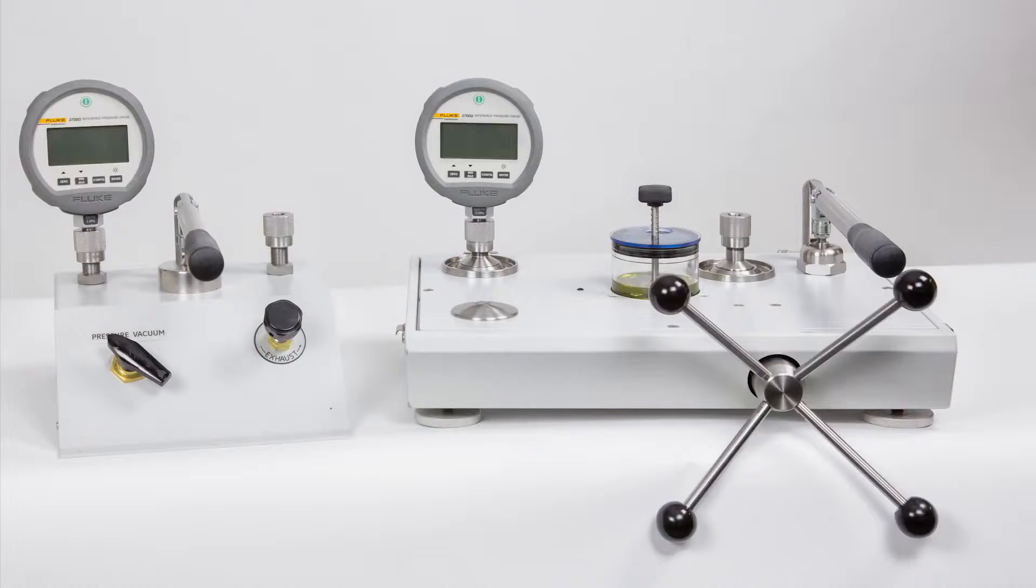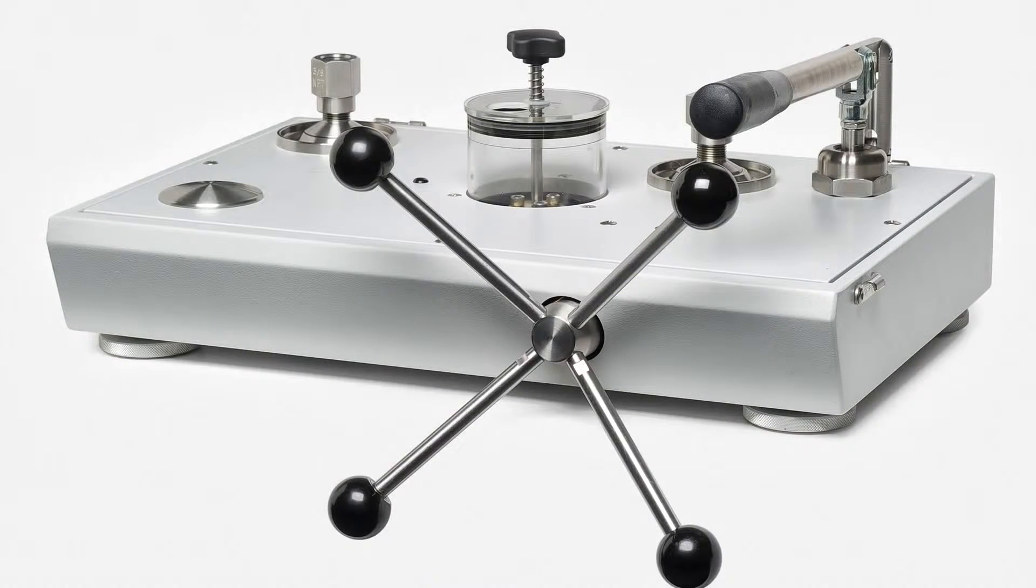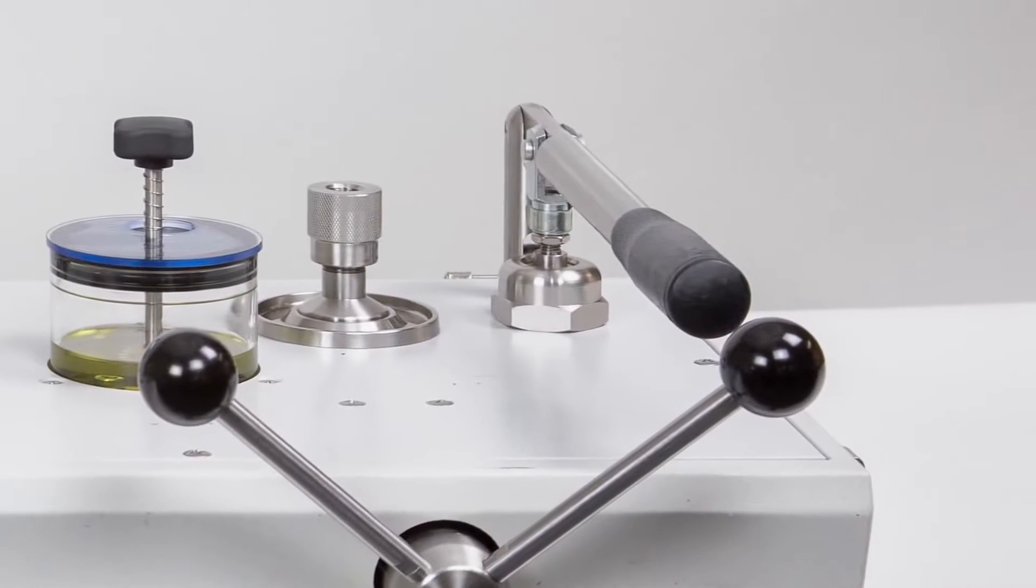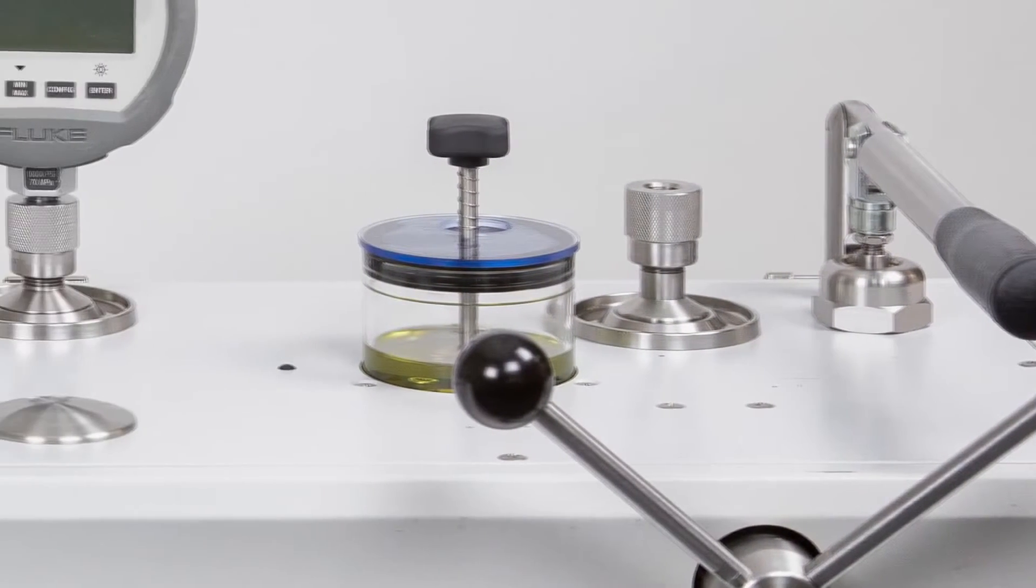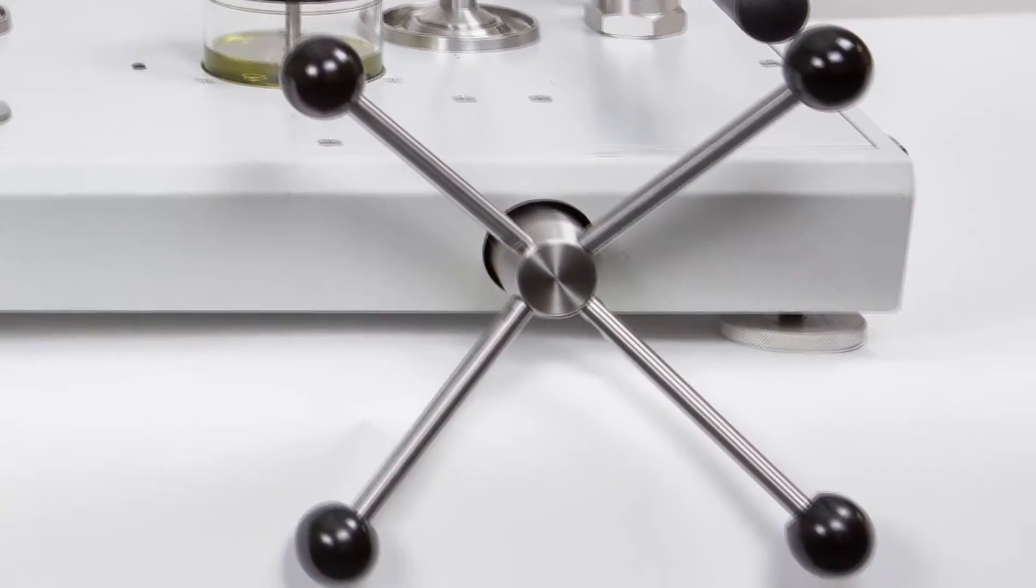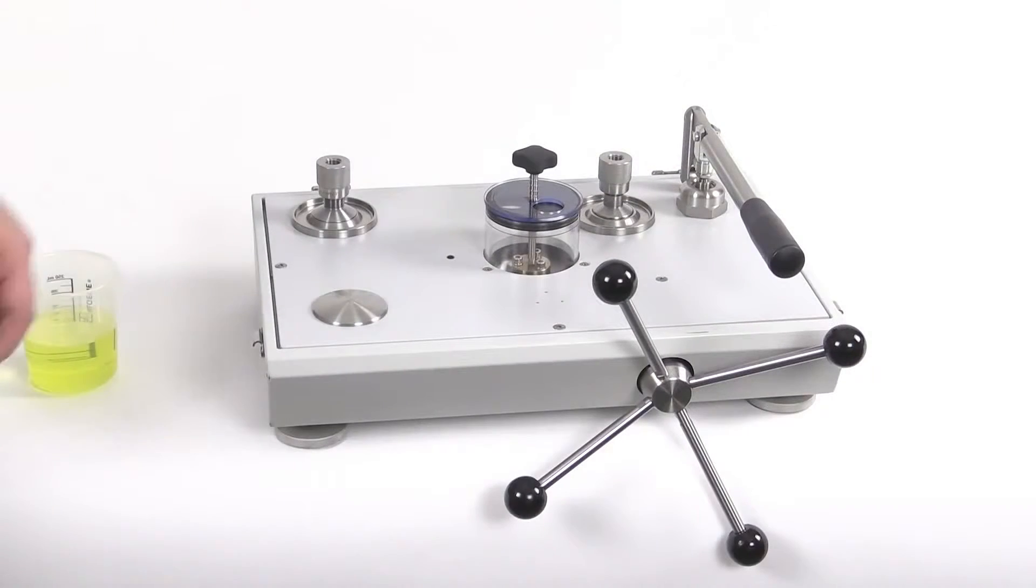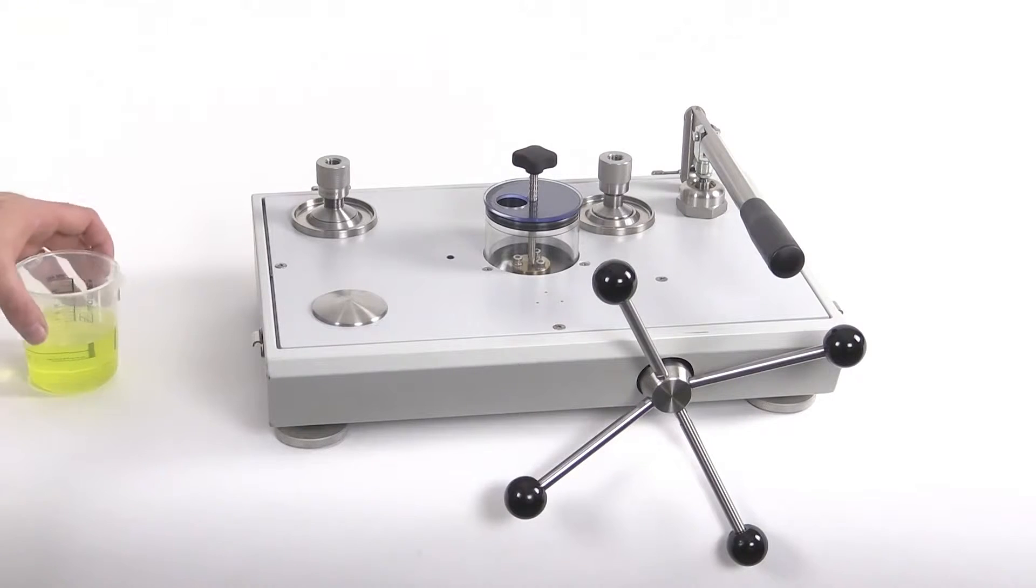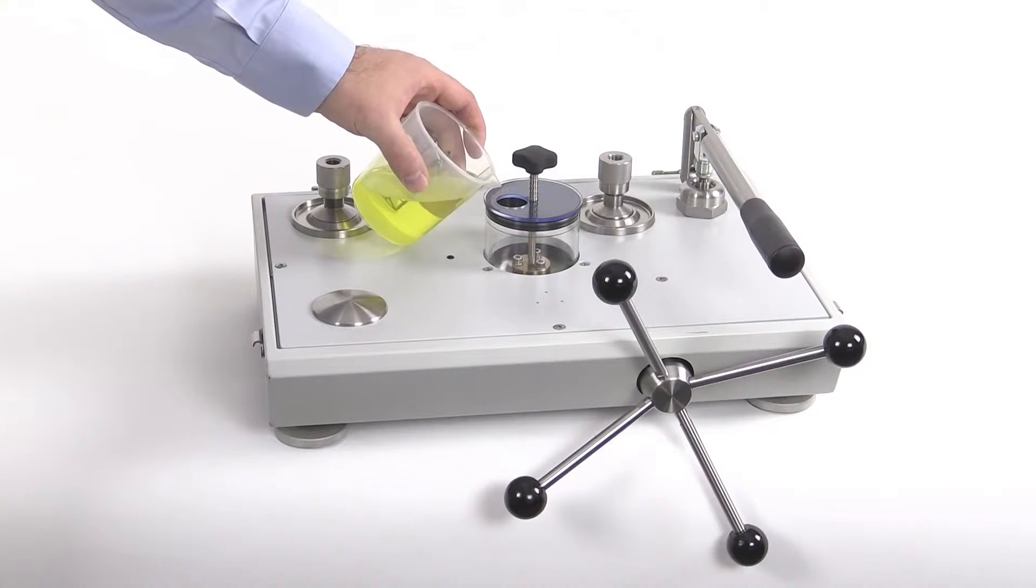This eliminates the potential of a pressure differential inside the system. The P5515 is capable of generating hydraulic pressures up to 140 MPa or 20,000 psi. It includes a built-in priming pump, clear acrylic reservoir, and screw pump. To fill the unit, rotate the dust cover until the fill hole is open, fill the reservoir with the appropriate fluid.